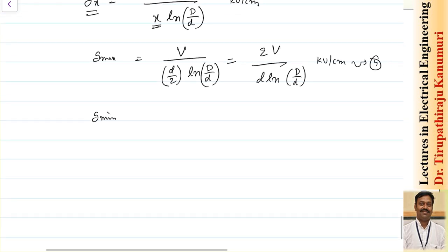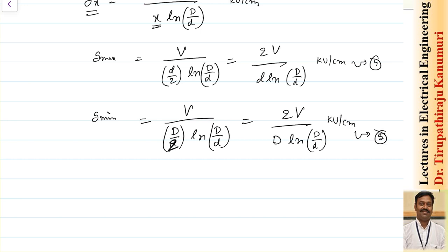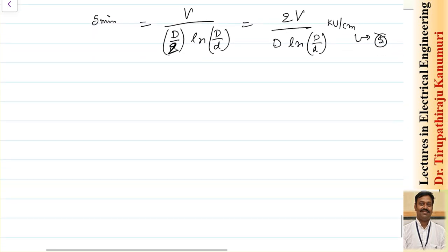Similarly, the minimum gradient occurs at the inner surface of the sheath (x = D/2): g_min = 2V / [D · ln(D/d)], in kV/cm. Let this be equation number 5. Taking the ratio g_max / g_min = D/d. Let this be equation number 6.